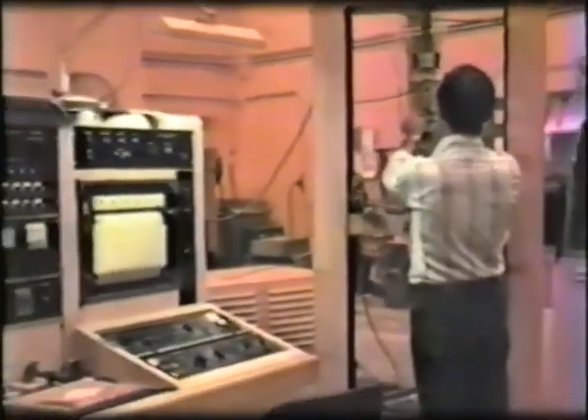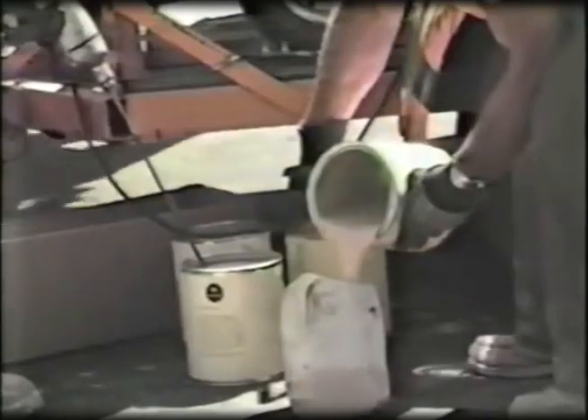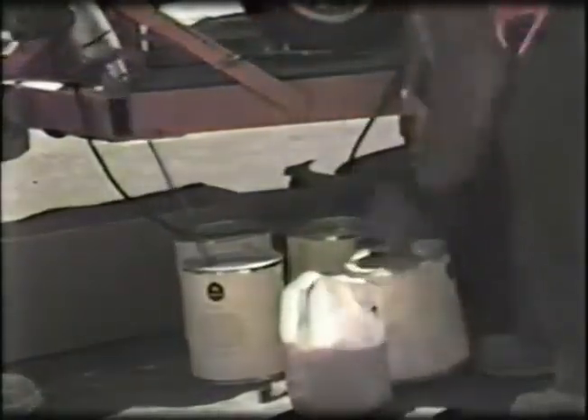A laboratory testing and evaluation program was developed by the Materials Bureau to produce specifications for acceptable sealants. Sealants were tested for curing time, water absorption, hot light, wire encapsulation, tensile strength, and adhesion. Based on this testing and extensive field evaluation, the best sealants for this purpose were found to be cold-poured epoxy or epoxy resin material. They have excellent bonding capability, are durable, resist effects of weather, and provide good encapsulation of the loop wire. These cold-poured sealants also diminish installation hazard and increase detector cost-effectiveness by reducing periodic maintenance.